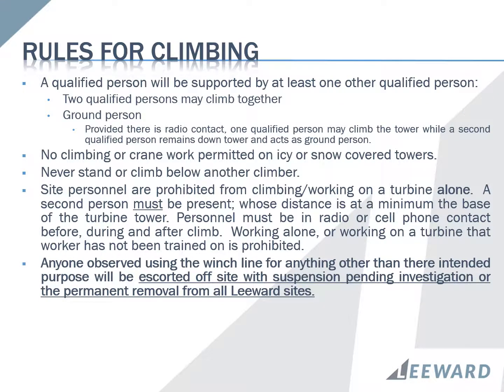A qualified person will be supported by at least one other qualified person. Two qualified persons may climb together, or a ground person. Provided there is radio contact, one qualified person may climb the tower while a second qualified person remains down tower and acts as a ground person. Unless pre-authorized by the supervisor, no climbing or crane work is permitted on icy or snow-covered towers. Never stand or climb below any other climber.